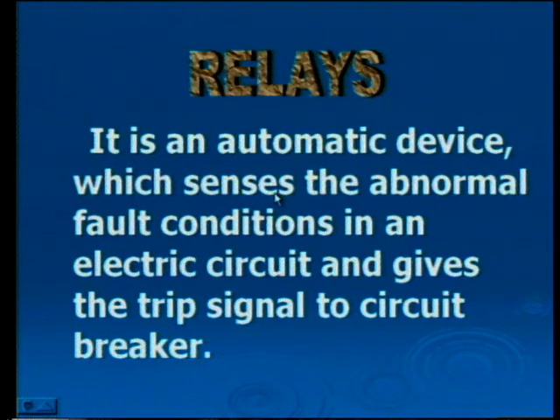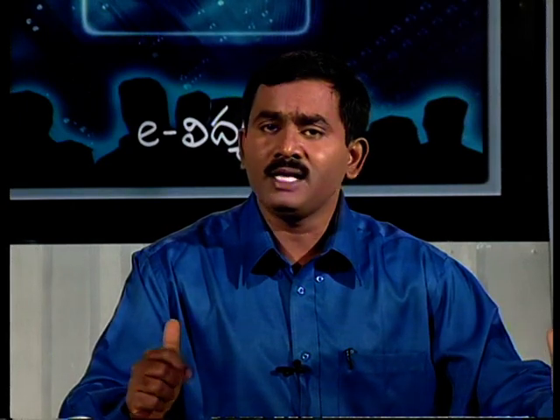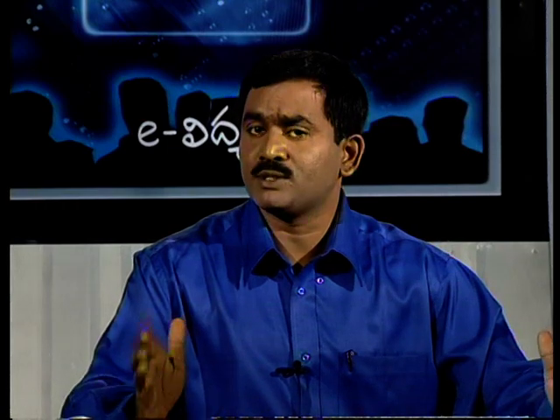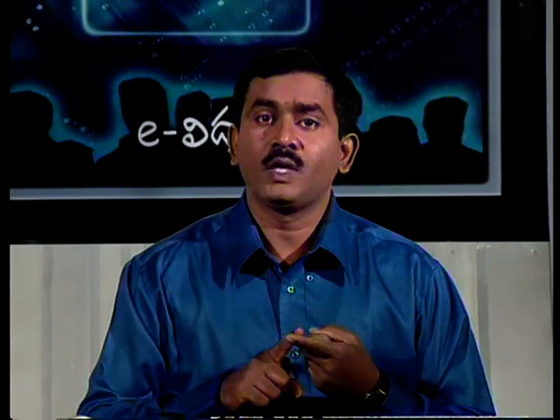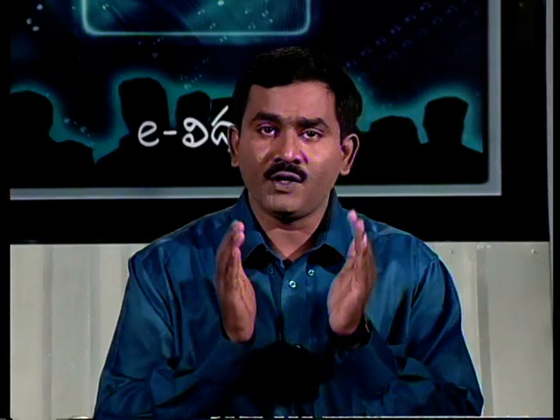A relay is an automatic device which senses the abnormal fault conditions in an electric circuit and gives the trip signal to the circuit breaker. Now, a relay is a static piece. It senses the abnormal conditions in the power system. How is it possible? Because in a power system, the main electrical characteristics are current, voltage, power factor or frequency, and phase angle or direction. Under normal conditions, these values are within limits. When any fault occurs in the system, these values are violated. The violated values are sensed by the relay coil, which gives a signal to the circuit breaker.